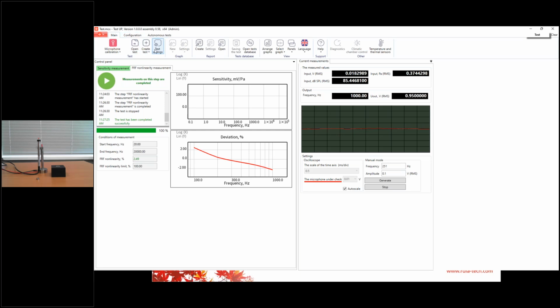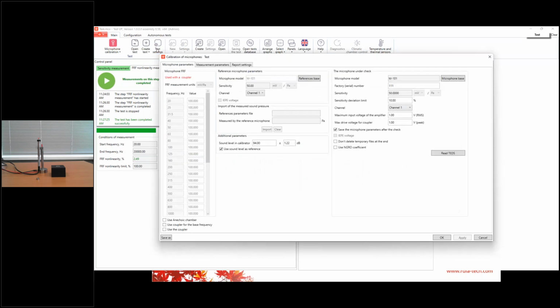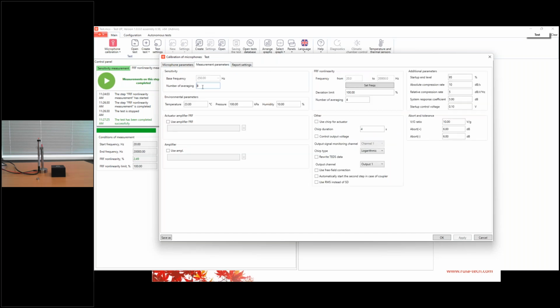Also, how long does this test run usually take? For example, if we want to calibrate our microphone from 0.1 Hertz up to 20,000 Hertz, with averaging number of 8, it may take, for example, 30 or 40 minutes. Now we will use our sine chirp. Here you see an option. I'll enter its duration to 6.